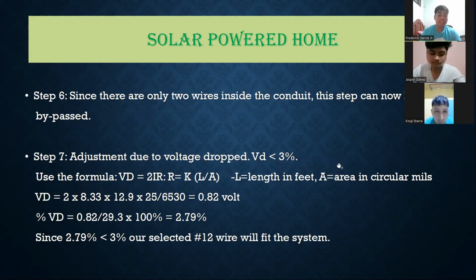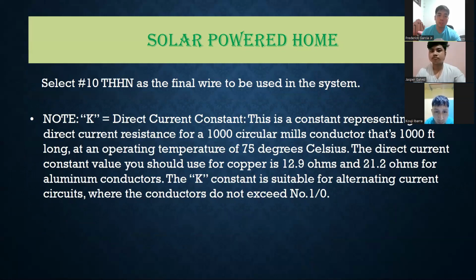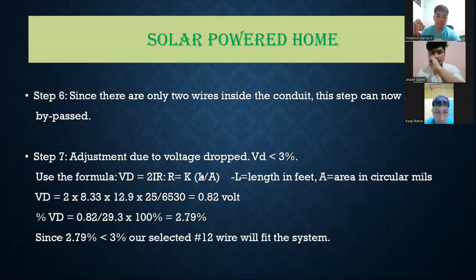Now then, for step 6, since there are only 2 conductors in the conduit, we don't need to do anything, thus the step is bypassed. Now for step 7, adjustment due to voltage drop, we'll say around less than 3%. Of course, this varies depending on the conditions. We use the formula VD equals 2 times I times R, where R can be K, this being DC, the direct current constant, multiplied by the length and divided by the area. Length in feet and area in circular mils. So now we have VD equals 2 times 8.33, which is the ISC.